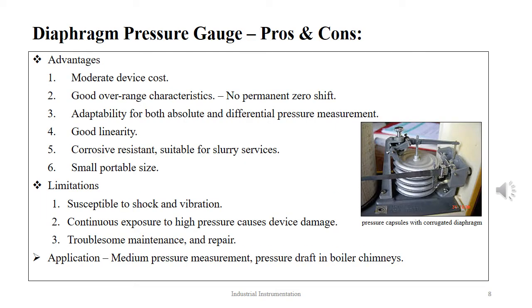The advantages of the diaphragm gauges are that they are of low to moderate cost. The device shows good overrange characteristics. It does not register any permanent zero shift. They are suitable for both absolute and differential pressure measurement. The device has linear output over a wide measurement range. They are suitable for both corrosive environments and slurry services.